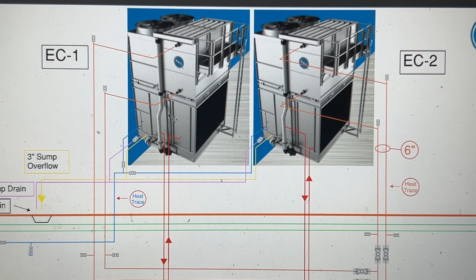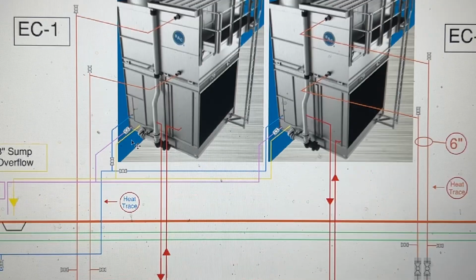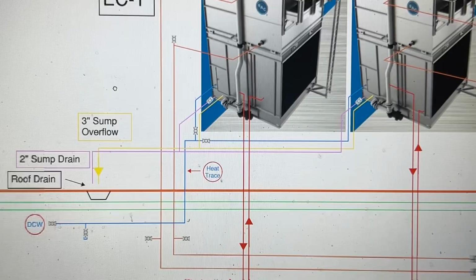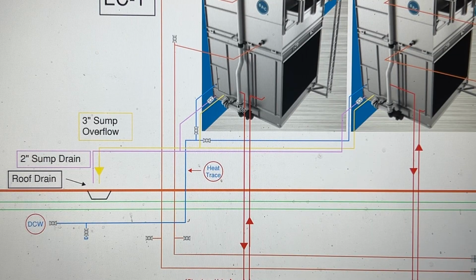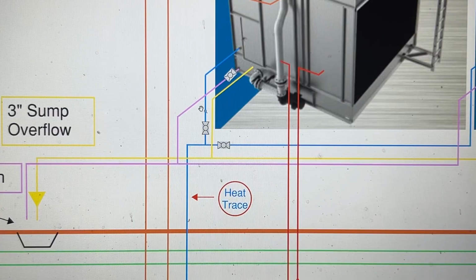So here we have just our supply and return going through the coil on this heat pump loop. We have, like I said before, that there is a sump at the bottom of the cooling tower here, which is what this pump draws to spray over the coil to cool it down. So this blue line here is our makeup water line, which if the water level in that sump gets too low, it will add more water to it so that it never dries out. We have a sump drain, which is this purple line here. So at any point, as part of the winterization process, we'll empty that sump through that line, and that goes to a roof drain on the roof.